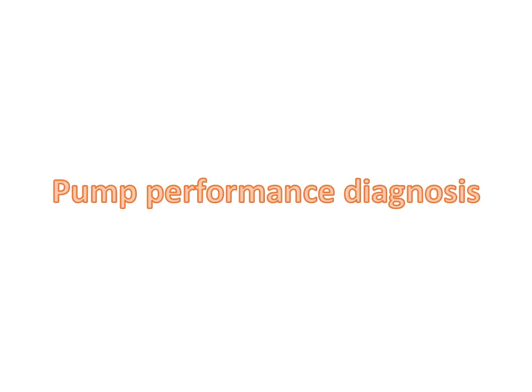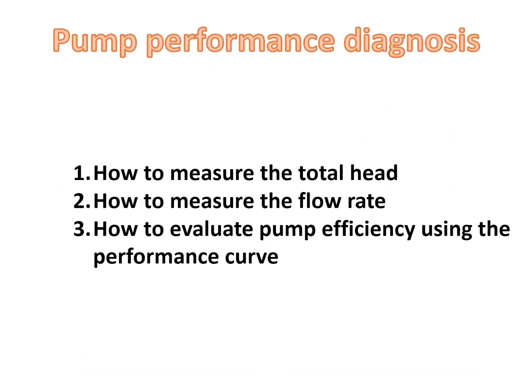Pump diagnosis is primarily performed by evaluating the operating efficiency. In addition, voltage and current are checked to assess the pump's condition and identify possible damage. If the measured total head and flow rate are found to be improper, the pump may be damaged, and continued operation under such conditions can lead to energy loss.